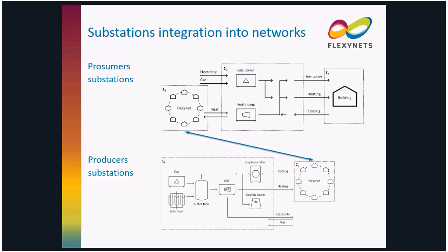On the other hand, this is another opportunity for the customer, who can also get cooling on the same pipeline from the network. By reversing the cycle of the heat pump, you can provide cooling to the building, and recover the waste heat from the building into the network itself. In this sense, the customer is not a customer anymore, but a prosumer, because it's producing and consuming thermal energy from and to the network.